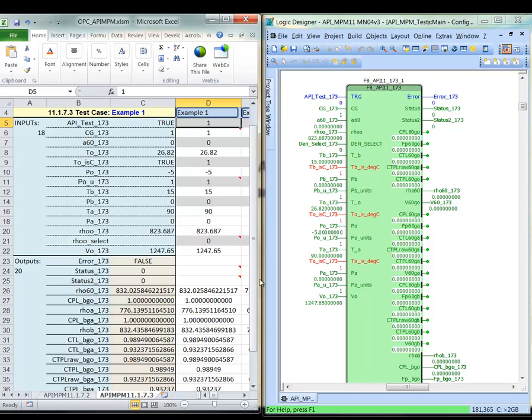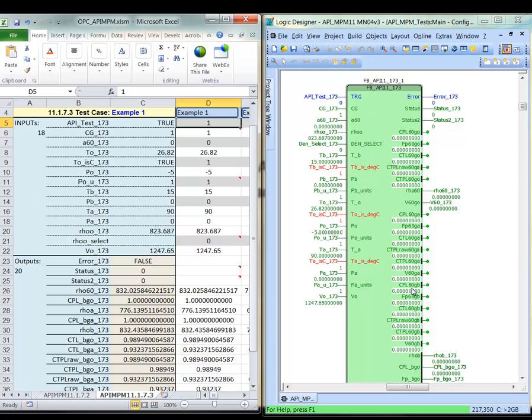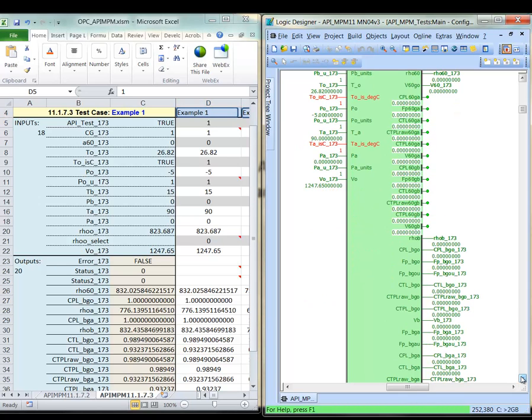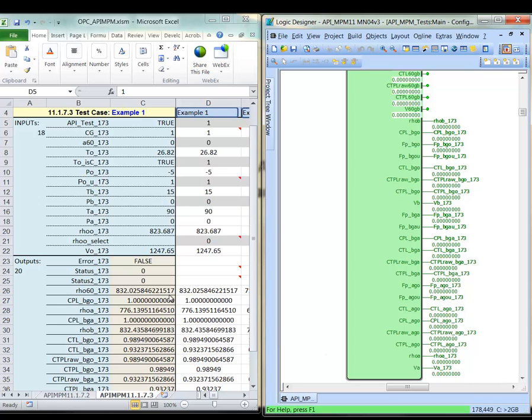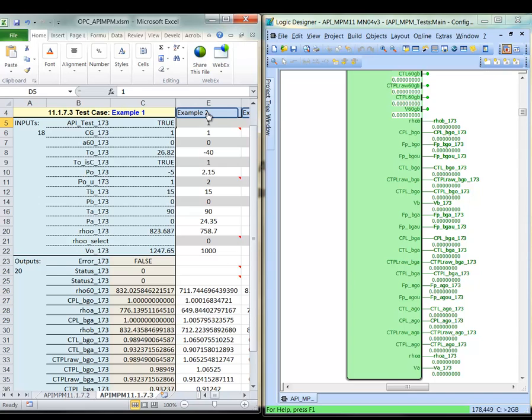You can see that they identically match. This is a longer function block because I'm generating a bunch of intermediary values for correction factors, correcting to base conditions, customary base conditions, as well as metric base conditions. If you use this function block, you can actually enter in either metric or customary units. So degrees Fahrenheit, degrees Celsius, PSI, kilopascals, bars, and you have a variety of options available to you. But in order to blow the screen up to see the actual values, I'm just going to show the output values here so that you can see what's calculated as we step through the examples.